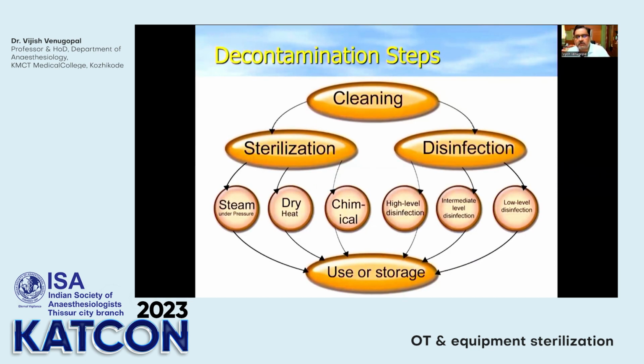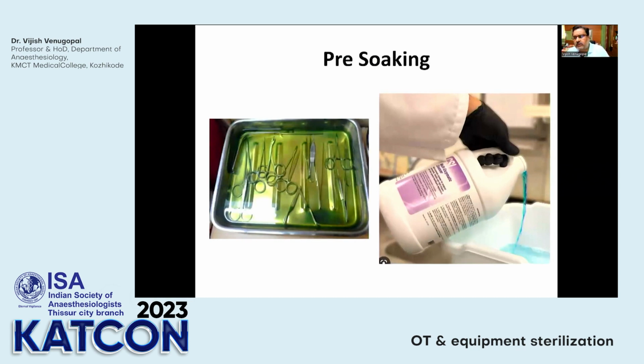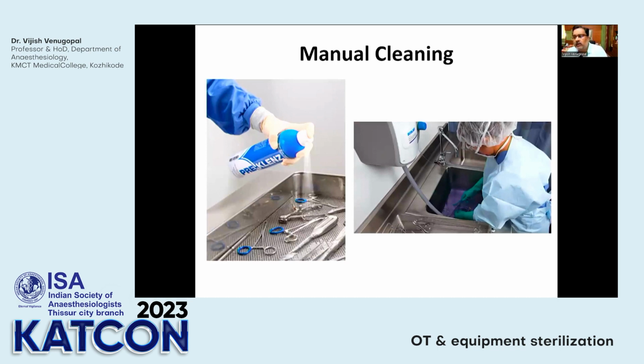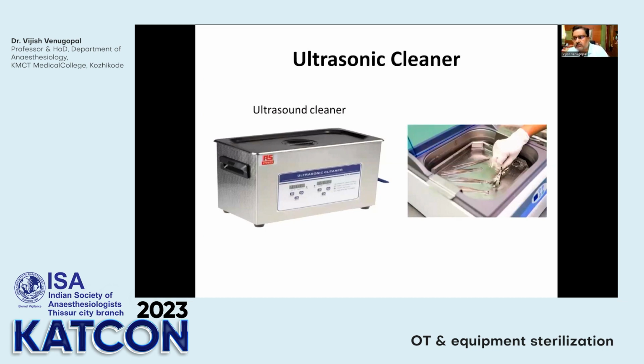So what are the different steps? The first step for decontamination is cleaning. This is followed by sterilization or disinfection, and then the equipment can be used or stored as per the requirements. Now, cleaning is a very important step because it helps in reducing the bioburden. So you can soak the instruments in sodium hydroxide or in an enzymatic solution. The enzymatic solution is really good because it helps in removing the non-visible coagulum that can be formed on these instruments, followed by either manual cleaning or automated cleaning. Manual cleaning can be done using brushes and high pressure water hoses, or you can use an ultrasonic cleaner, which sends ultrasound waves and agitates the water in the system.